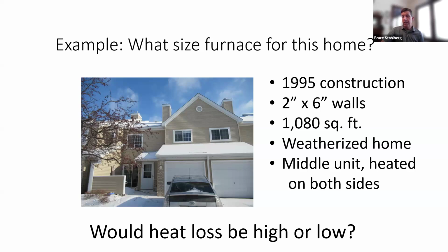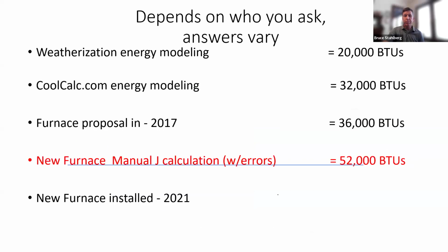So usually pretty tight construction in 1995. Not a huge home at around 1,100 square feet. And it's a middle unit. So that's important because on both sides, we are going to be having another home that's heated at 65 to 70 degrees. So would the heat loss be high or low on this unit? And in my opinion, it'd be quite low because we don't really have much of a load here.